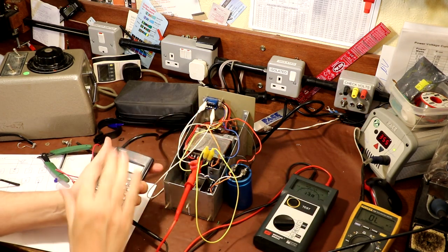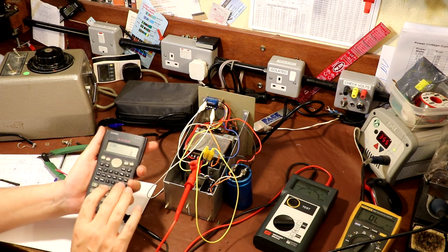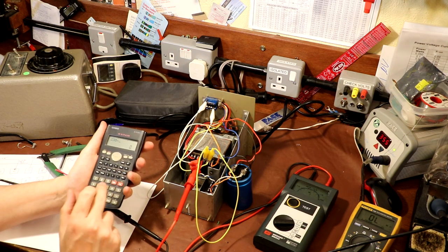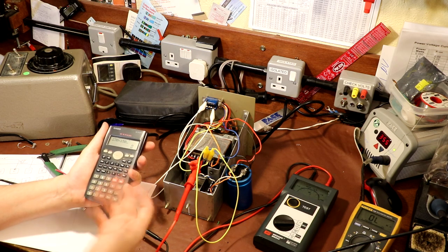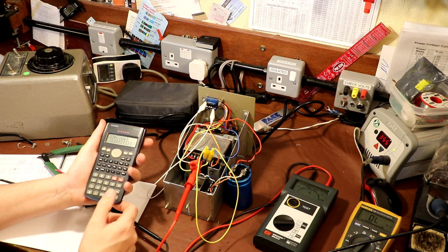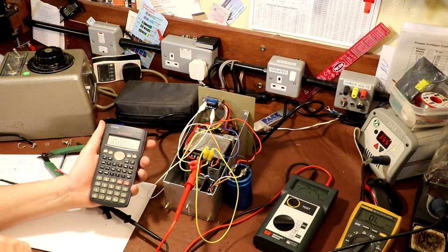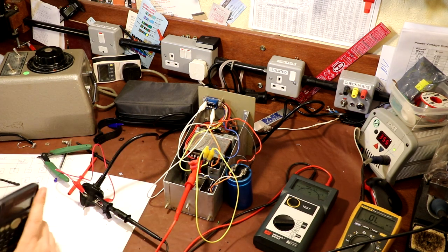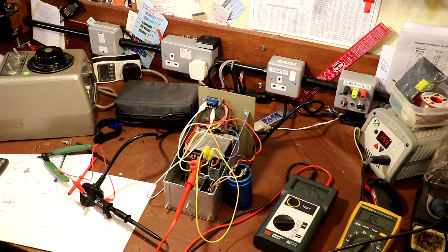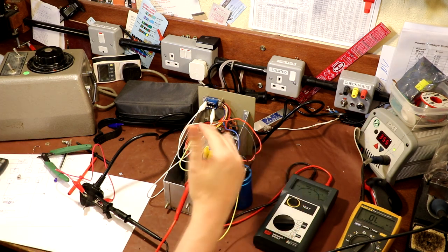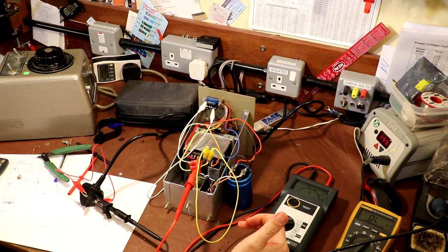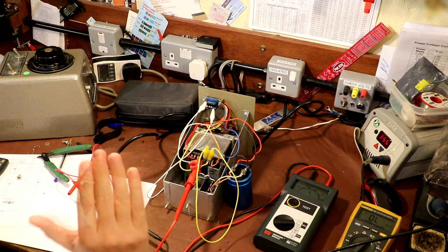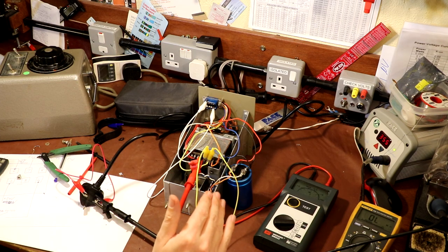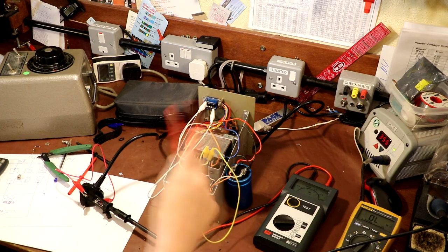So the main supply voltage is 230 volts, and 230 volts across 150 megohm, call it 10^6, equals 1.5 microamps. Now 1.5 microamps isn't enough to trip an earth leakage circuit breaker. So although there's a little bit of leakage between the primary and secondary here, it shouldn't be tripping the earth leakage circuit breaker in my consumer unit, but it certainly is tripping it out. It's done it 2 or 3 times now, and I can't really explain why.